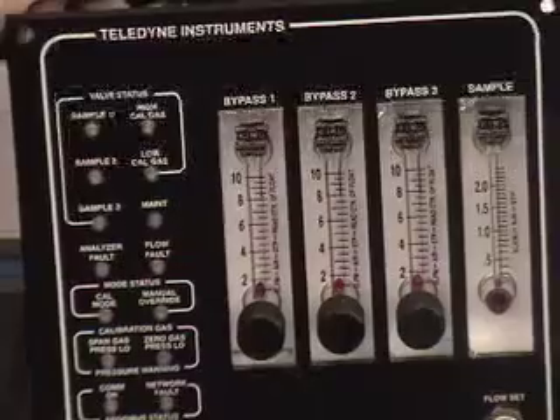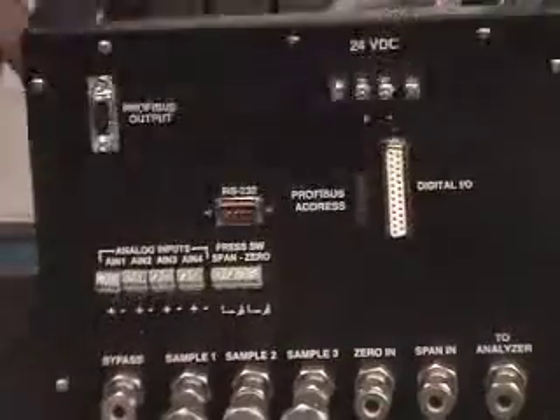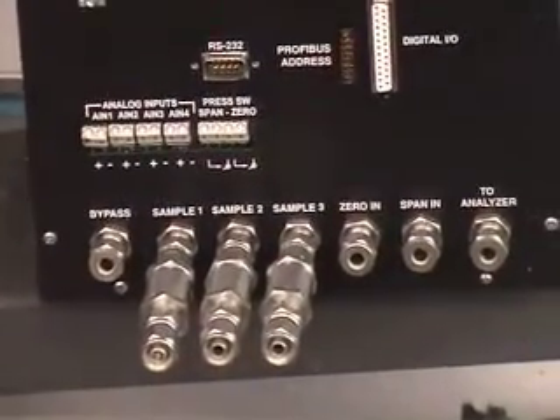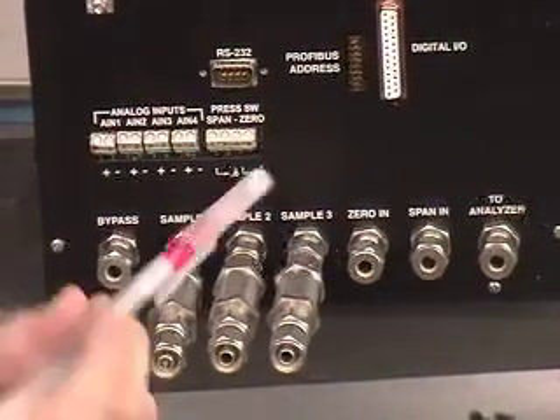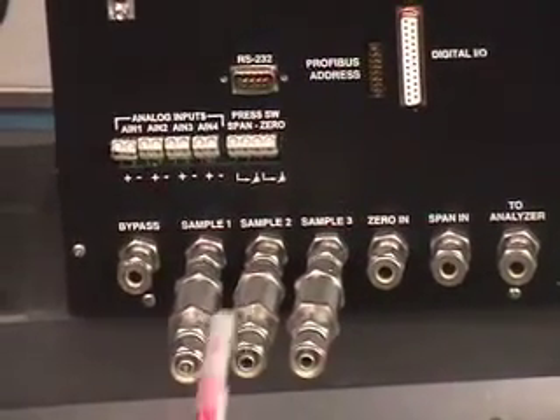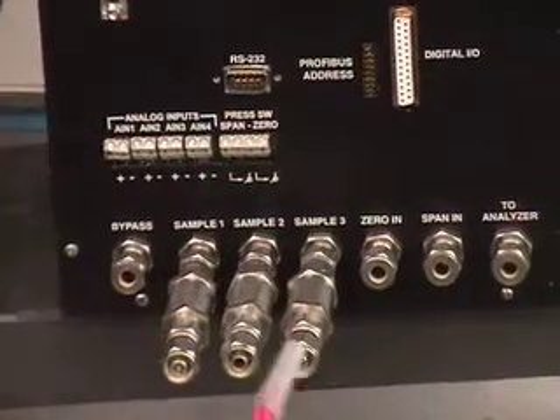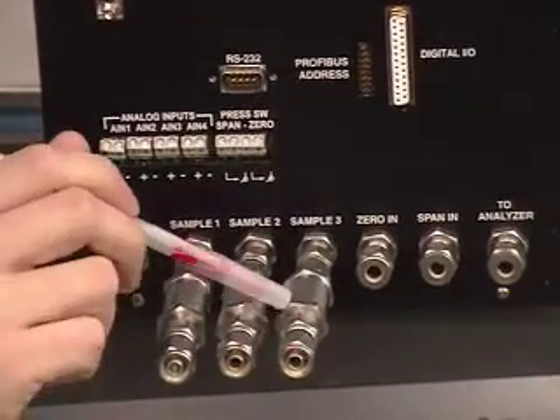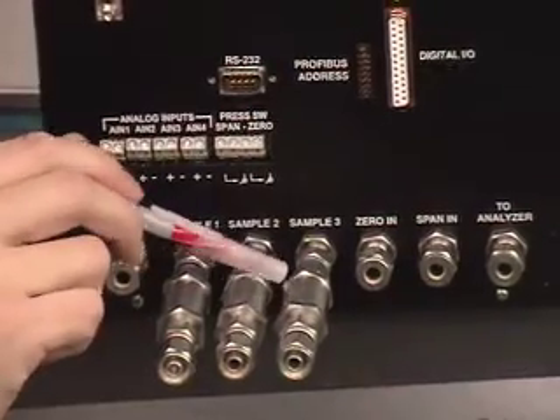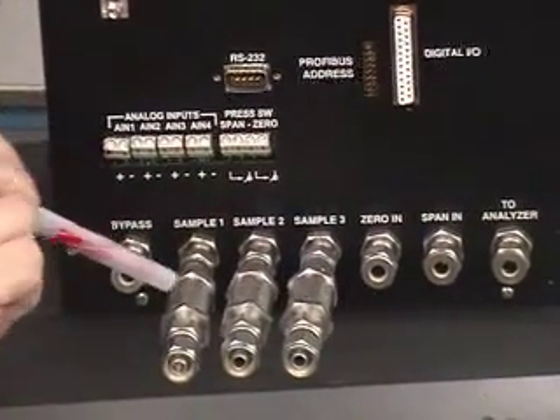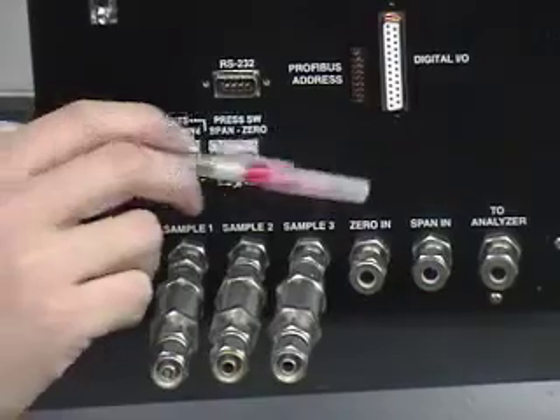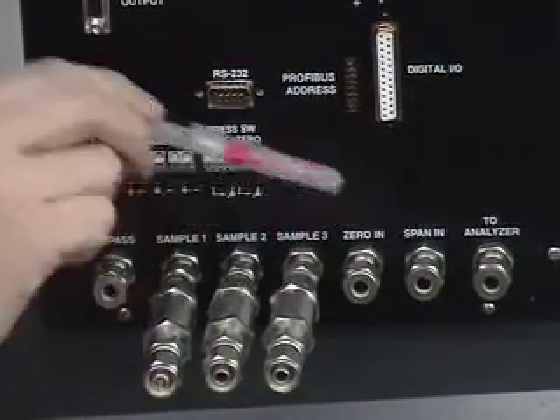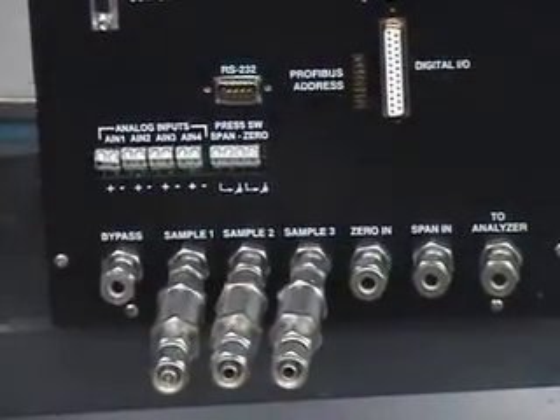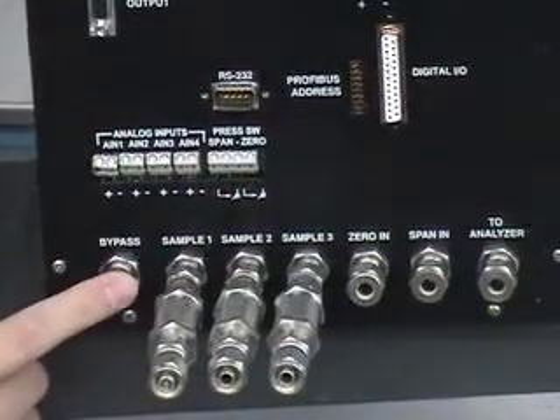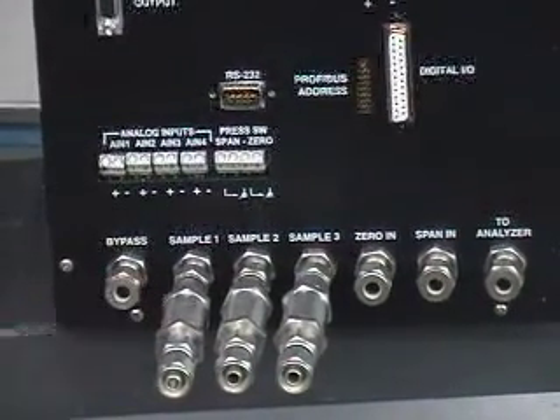Let me show you the back. On the back, we've got all the fittings for the gases. Like I was saying, we can select 3 sample gases, and we have sample 1, sample 2, and sample 3. These are the inlets, and the gas goes through these micron filters to capture particulates. We've got an inlet for zero gas, and an inlet for span gas. And for the 3 samples, we have a bypass outlet, and we've got the outlet that will go to the analyzer.